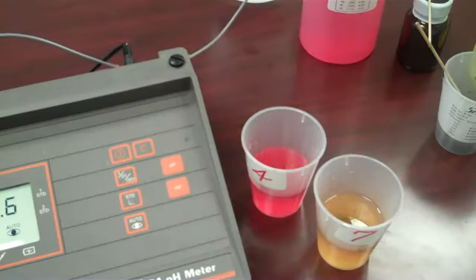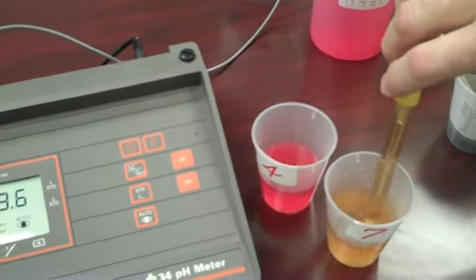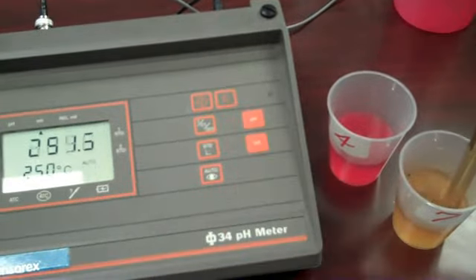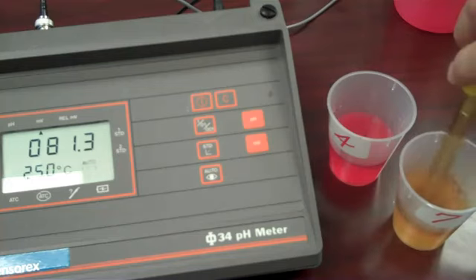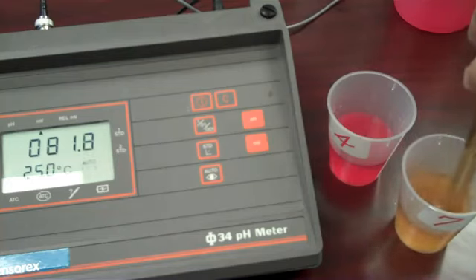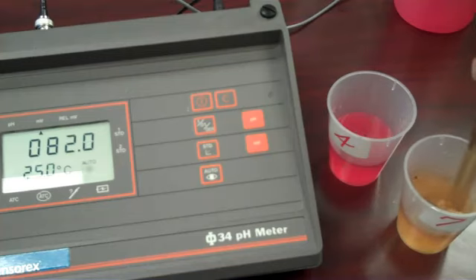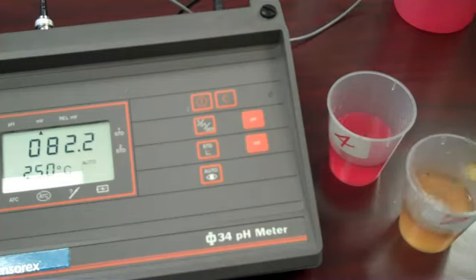At 25 Celsius, the 7 buffer will have an ORP value of about 90 millivolts. In this example, my ORP sensor is outputting something close to 82. As long as we're within plus or minus 15%, the readings are known to be good.